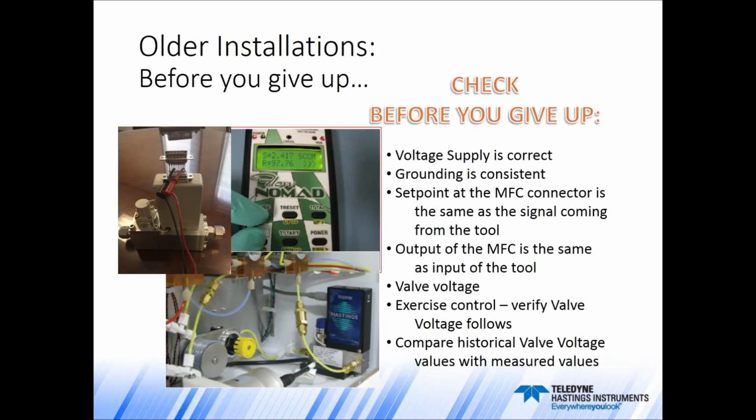When you go to the next slide, this is where, if you actually decide that you have to remove the flow controller from the system, based on all the things that you know about the system, about the flow controller, and some of the things that you've learned maybe in this webinar, there's a couple of things that we want you to do, if you have the time, just to make sure that everything is all right. The voltage supply of the flow controller. So we developed this quick checklist.